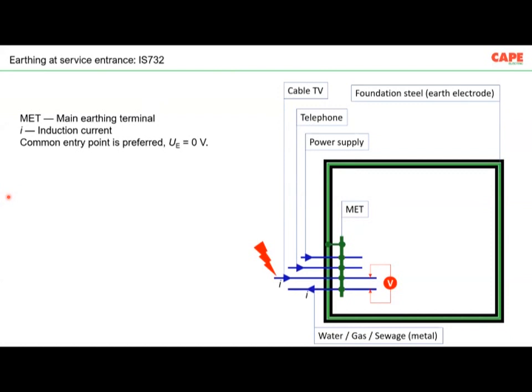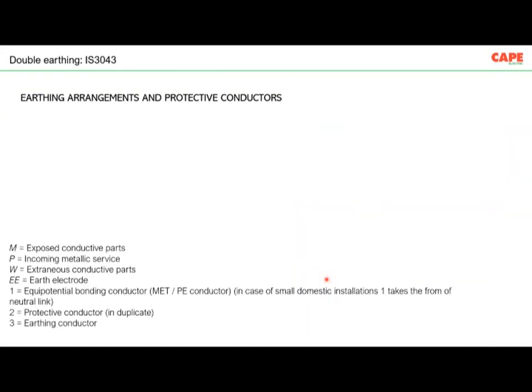Number two, in case of a lightning strike on the building or on the service line, the potential differences, the voltage between two service incomings, are reduced to a very low level. Number three, this protective equipotential bonding also reduces the shock voltage in case of a fault on the high voltage side of the transformer. Imagine you have an HT transformer and there is a fault on the HT side. This fault sometimes creates a shock hazard inside your building. But this protective equipotential bonding will provide safety against all these three. So there are three purposes for this protective equipotential bonding at the service entrance.